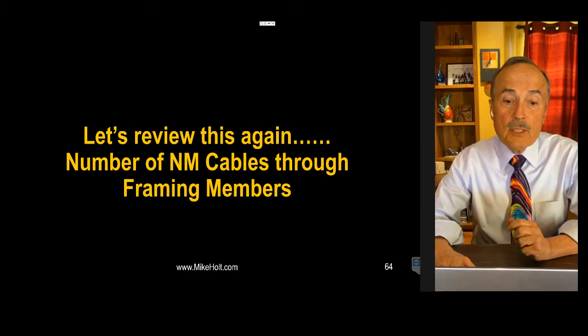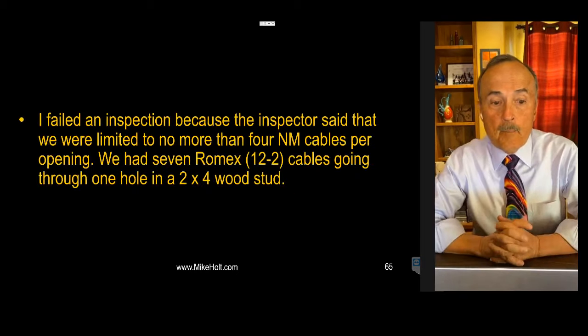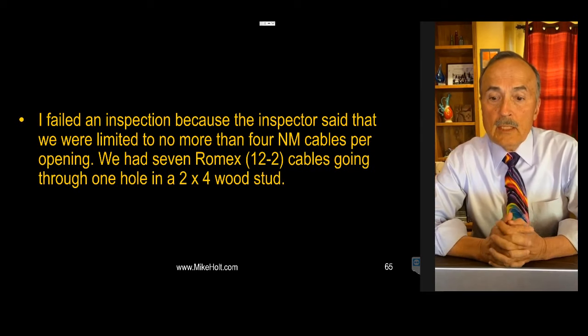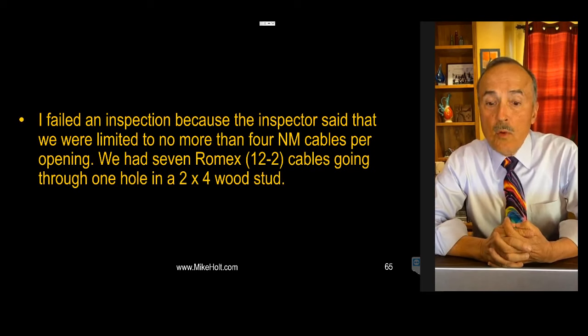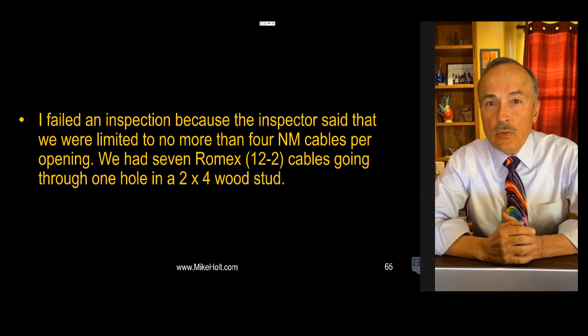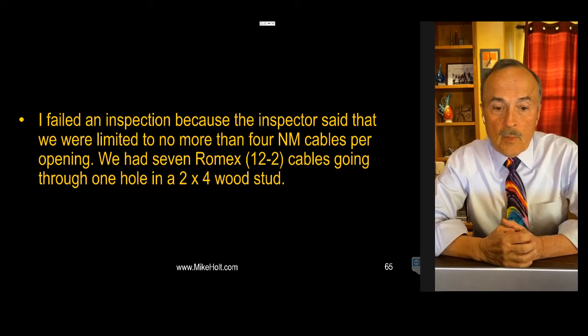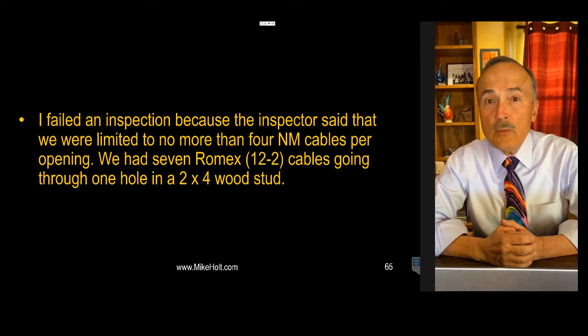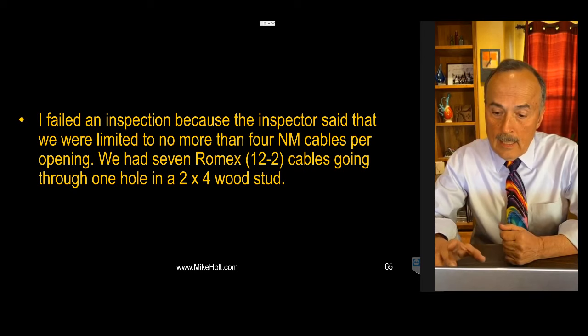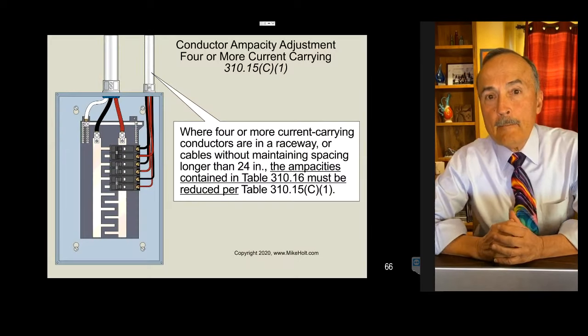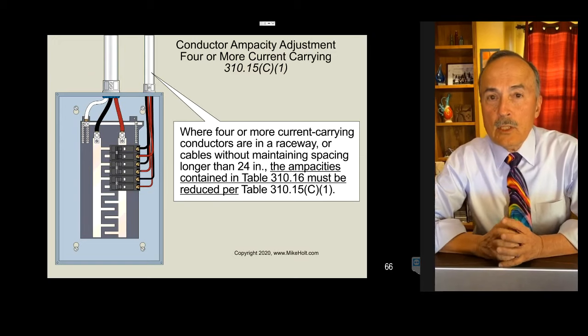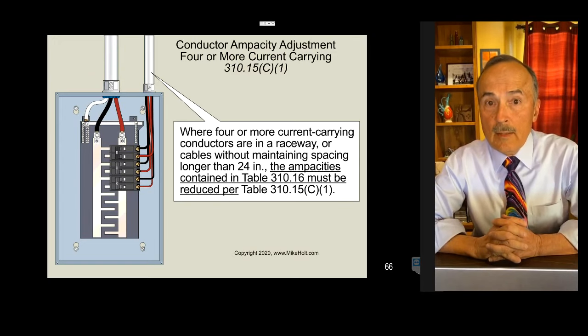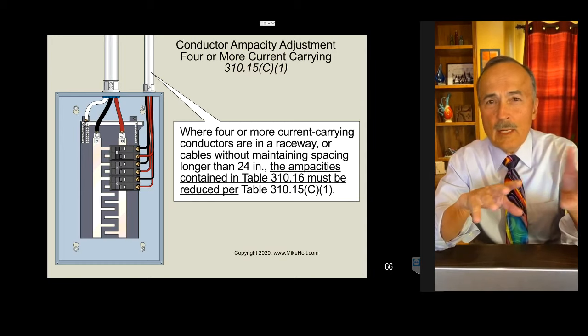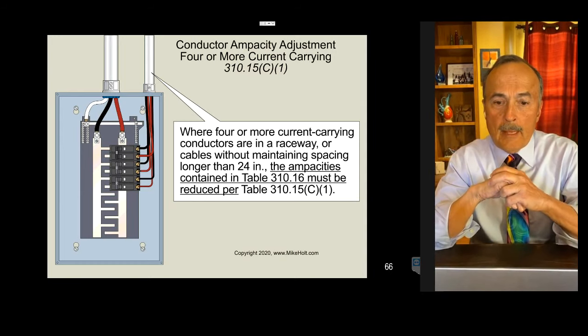Let's review this again. I got a bunch of comments after I got done last night about the Romex bundling and running through a framing member. How many NM cables can you run through a framing member? And here was the question. Mike, I failed an inspection because the inspector said that we were limited to no more than 4 NM cables per opening, meaning like a drilled hole through wood or maybe the metal framing members. We had 7 Romex 12-2 cables going through 1 hole in a 2x4 stud.